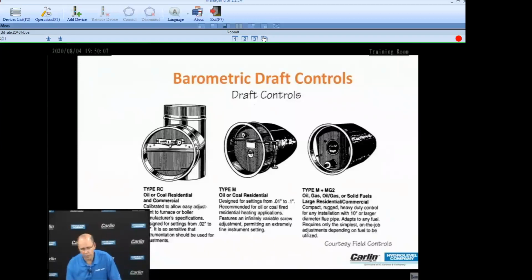What was the cause? It's not the barometric. The barometric didn't cause the flue gases to back up. There's a different problem. That's what needs to be addressed. The barometric is there for a reason. It needs to be applied correctly.